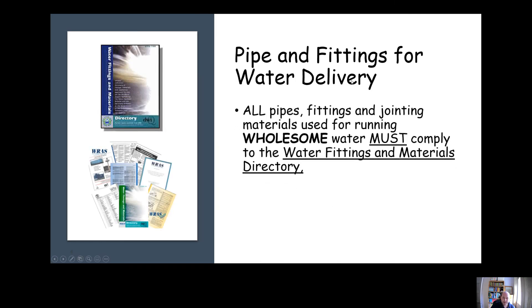All pipes and fittings that are used on wholesome water supplies must comply with the Water Materials and Fittings Directory, which is written by WRAS, the Water Regulations Advisory Scheme. This sets out that the fittings and pipework must not corrode or otherwise contaminate the water supply, and it's a legal requirement to use fittings from this directory that meet this standard.